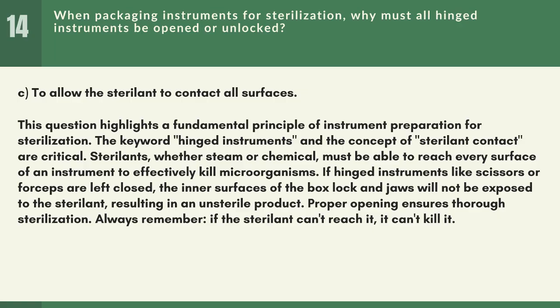If hinged instruments like scissors or forceps are left closed, the inner surfaces of the box lock and jaws will not be exposed to the sterilant, resulting in an unsterile product. Proper opening ensures thorough sterilization. Always remember, if the sterilant can't reach it, it can't kill it.